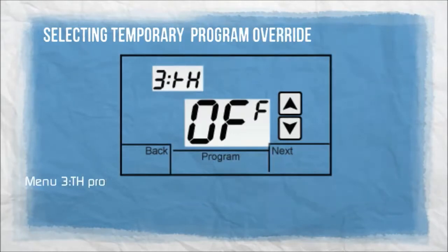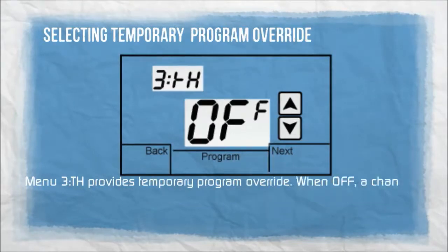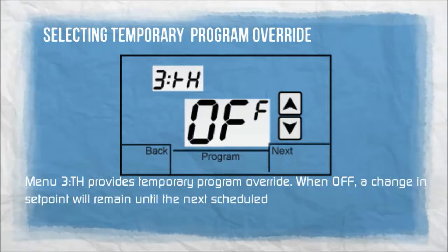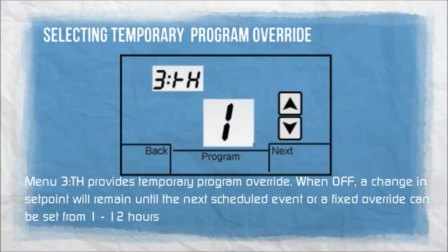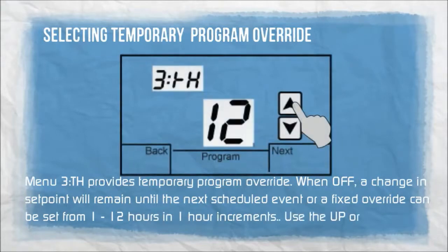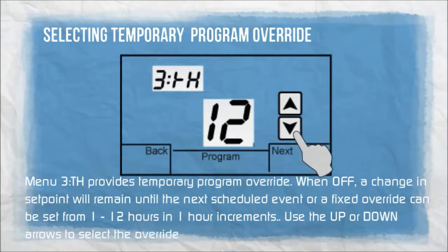Menu 3TH provides temporary program override. When off, a change in set point will remain until the next scheduled event, or a fixed override can be set from 1 to 12 hours in 1-hour increments. Use the up or down arrows to select the override time. The factory default is off.